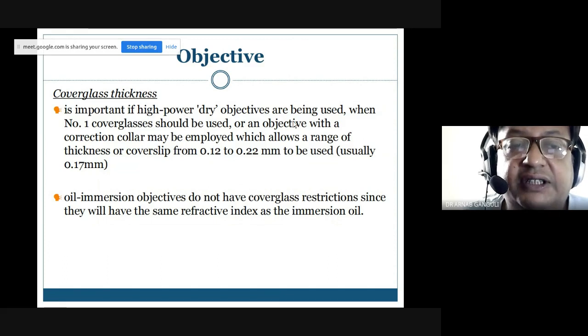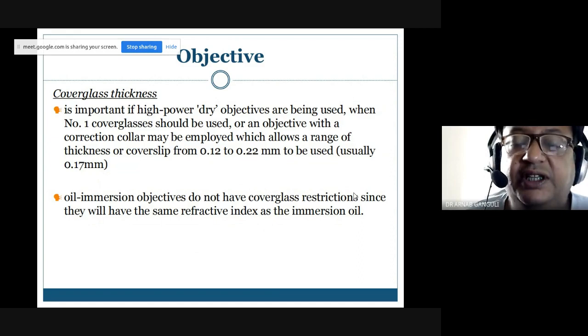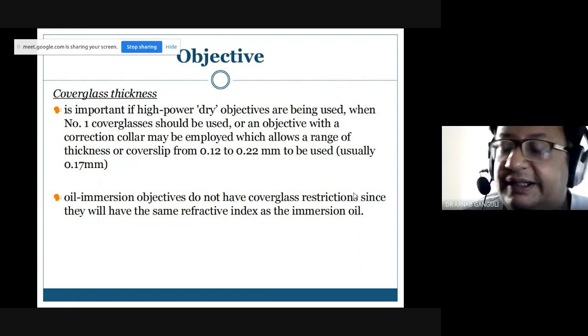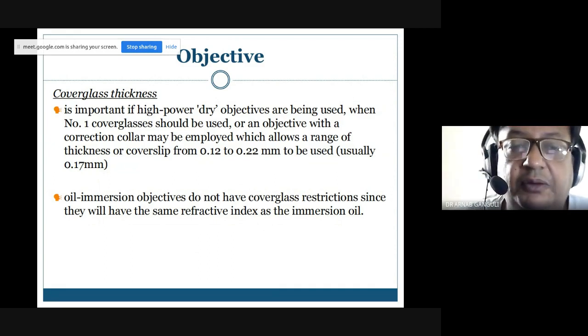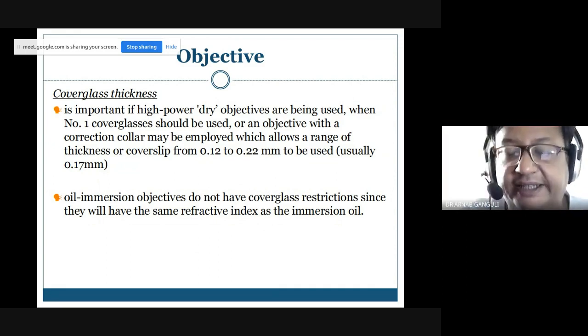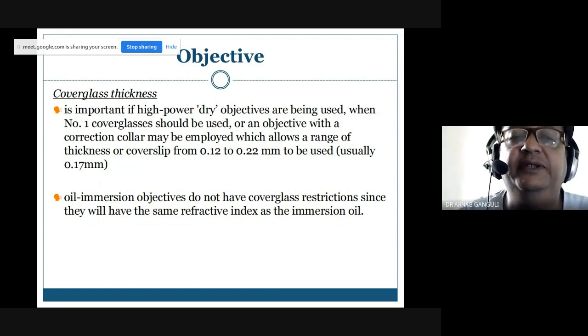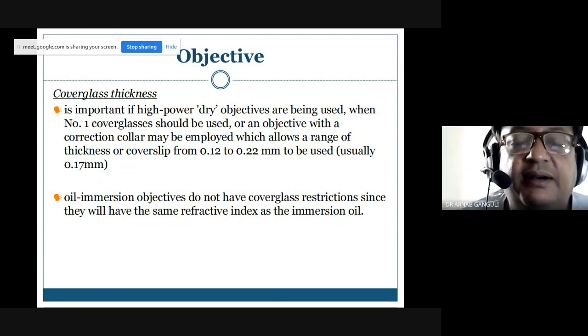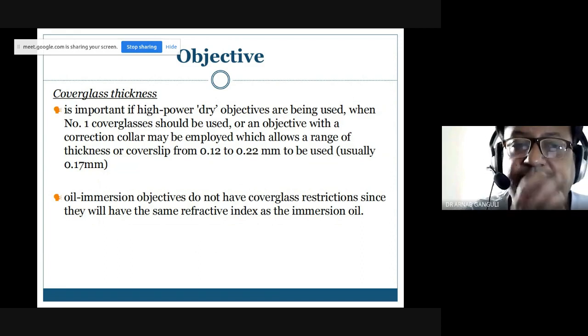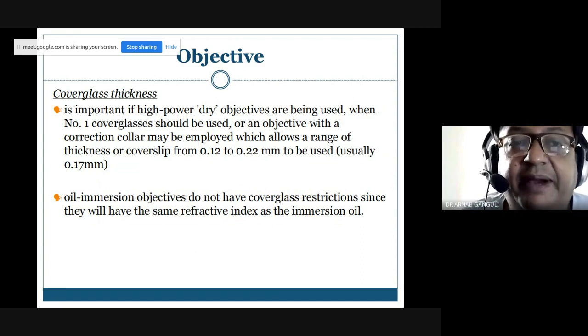So the thickness of the cover slip is very important. Oil immersion doesn't have cover glass restrictions, since the glass has the same refractive index as the immersion oil. In oil immersion, you put a drop of oil on top of the object, and the objective lens is also dipped in the oil. So all the light is not coming from the air. Directly it is going into the oil, and from the oil it's directly going inside the objective lens. The image is going.